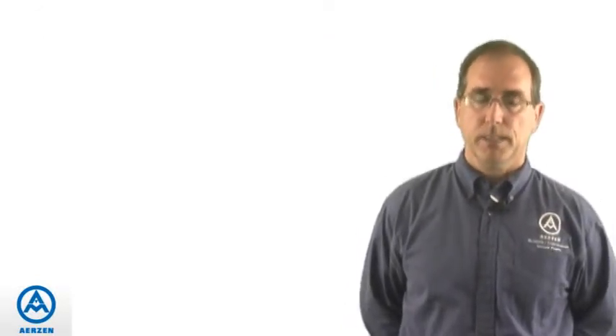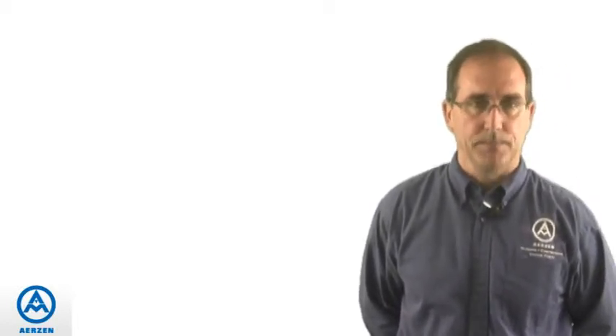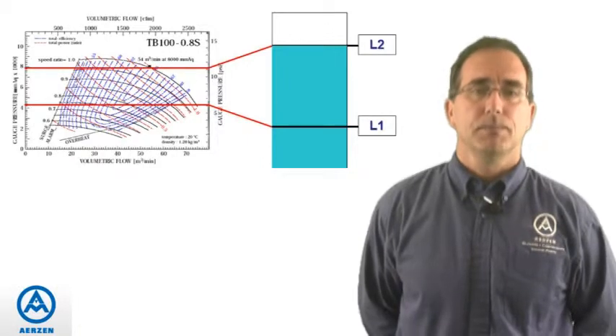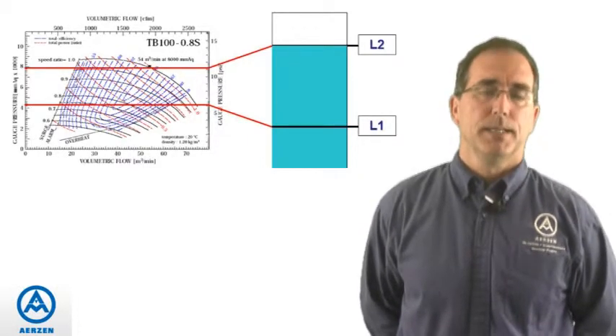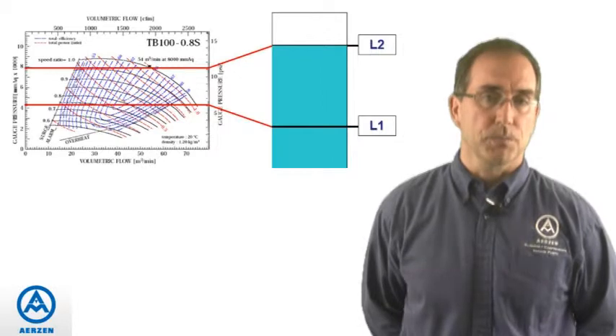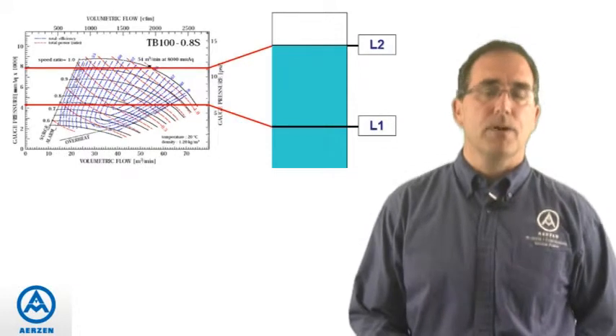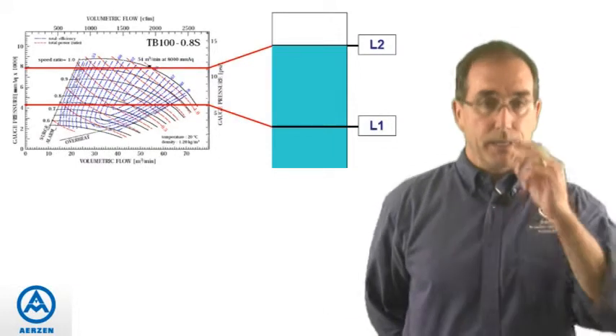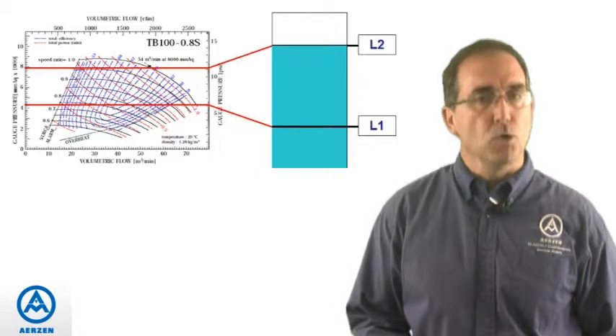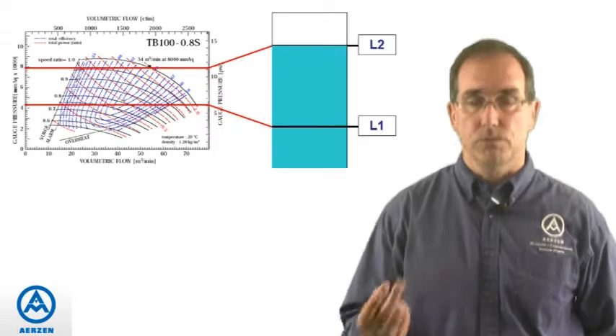Putting aside the economics for a second, let's look at some system characteristics that would also help determine the best technology. One of those characteristics is pressure variation. Either of the two PD technologies would be appropriate for a system with major pressure fluctuations, because all you really need is enough motor horsepower to overcome the higher pressure — L2 in this diagram. However, if you were using a turbo technology, you would have to make sure that both the high level and the low level reside on the performance map, otherwise you would run into trouble.